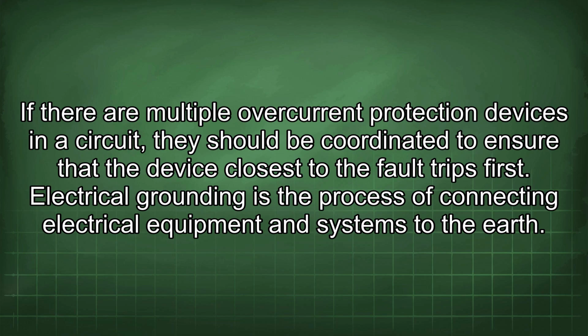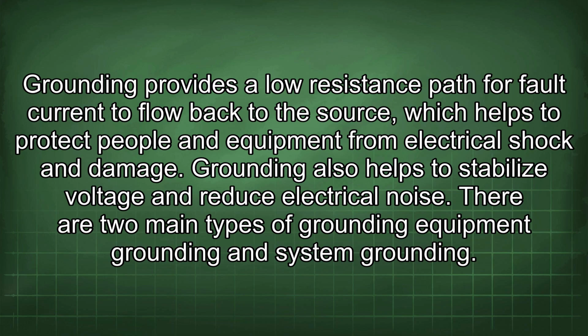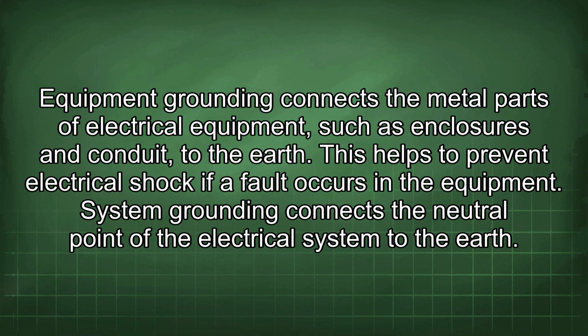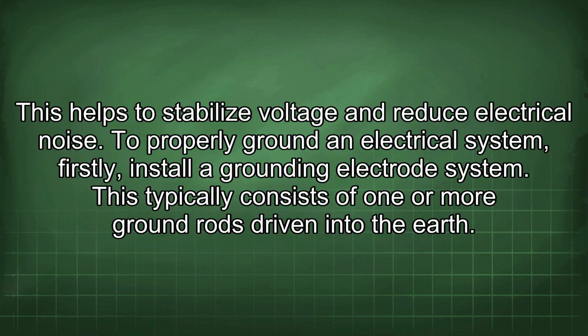Electrical grounding is the process of connecting electrical equipment and systems to the earth. Grounding provides a low resistance path for fault current to flow back to the source, which helps to protect people and equipment from electrical shock and damage. Grounding also helps to stabilize voltage and reduce electrical noise. There are two main types of grounding: equipment grounding and system grounding. Equipment grounding connects the metal parts of electrical equipment, such as enclosures and conduit, to the earth. This helps to prevent electrical shock if a fault occurs in the equipment. System grounding connects the neutral point of the electrical system to the earth. This helps to stabilize voltage and reduce electrical noise.